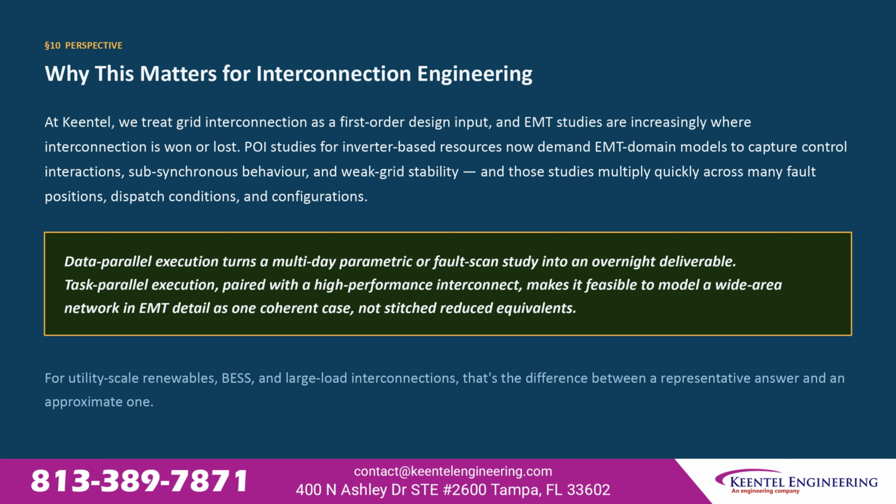Point of interconnection studies for inverter-based resources now require EMT domain models to capture control interactions, subsynchronous behavior, and weak grid stability. And those studies multiply quickly across many fault positions, dispatch conditions, and configurations. Data parallel execution turns a multi-day parametric or fault scan study into an overnight deliverable.